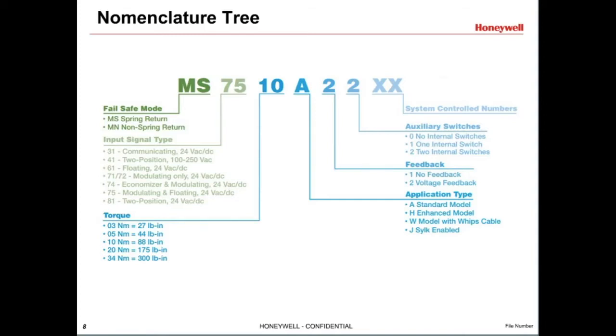While we are here, notice the codes for the other control signals. For instance, 31 is for communicating actuators, 41 is for two-position line volt, and 61 is for floating 24-volt. The next letter is A, and this is for standard actuators. If it were J, it would be a Sylk communicating actuator. It would then also have a 31 in the first part of the number, as it would be a communicating actuator.